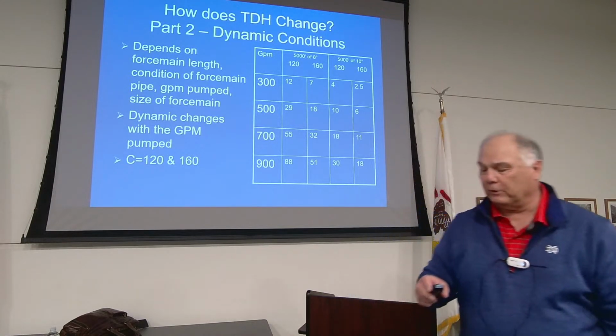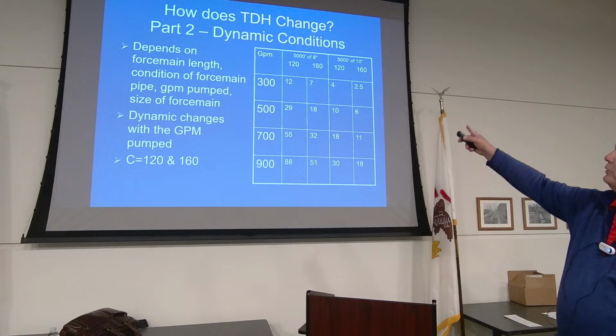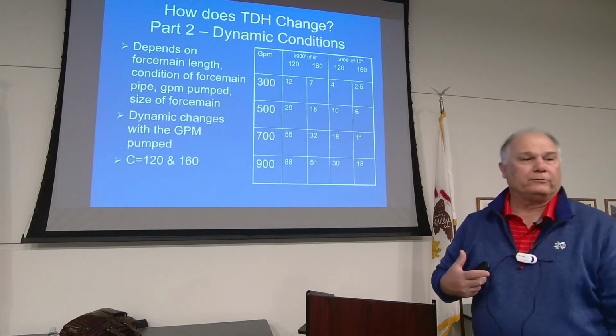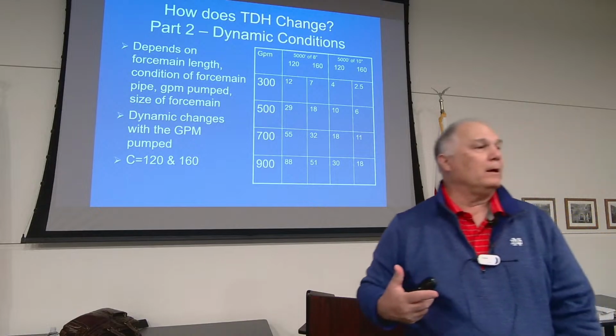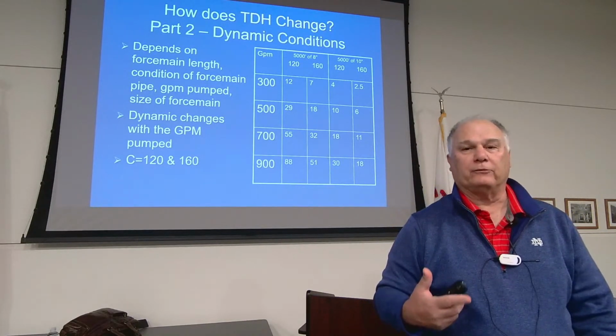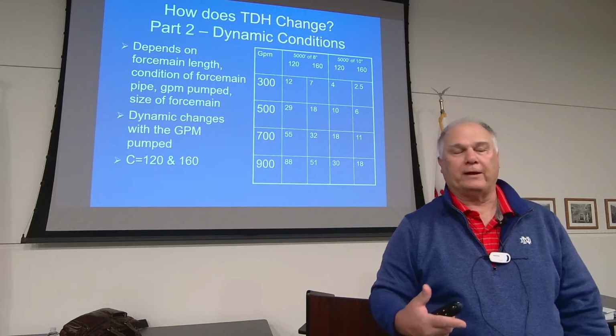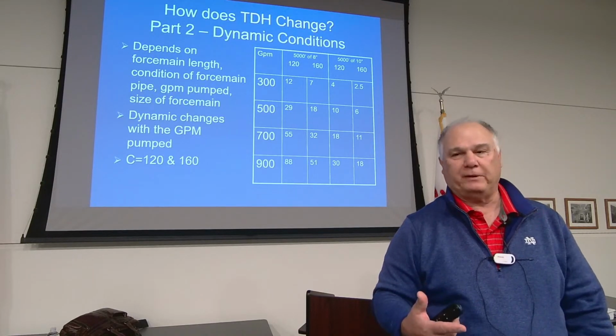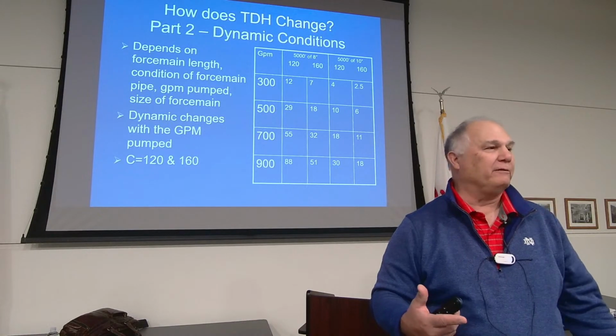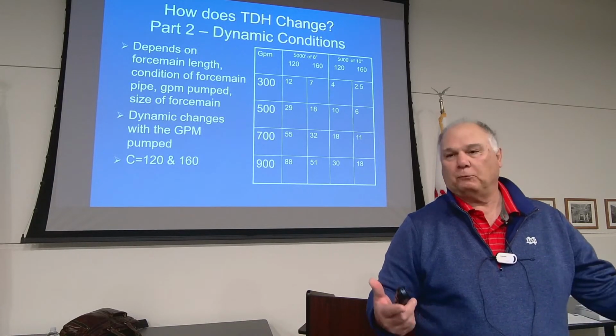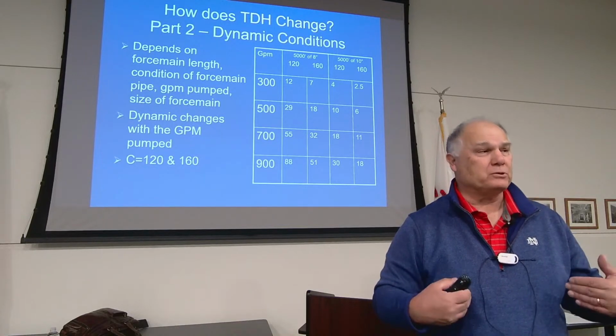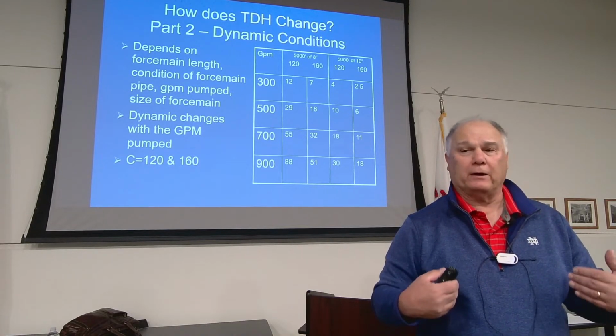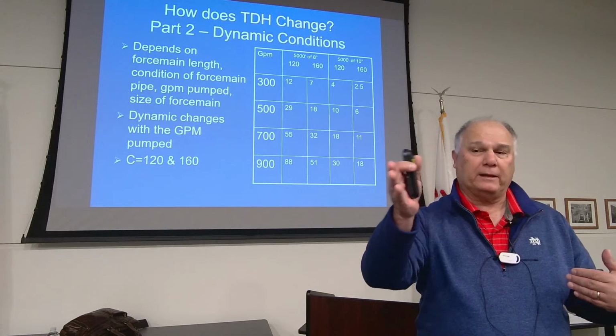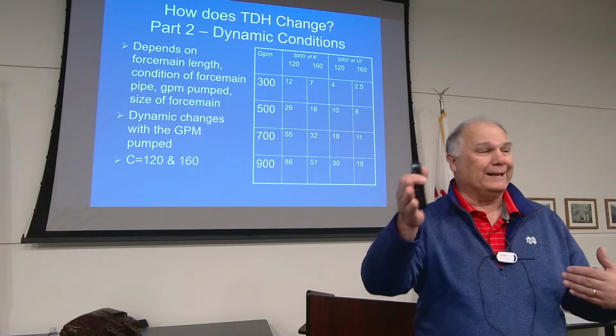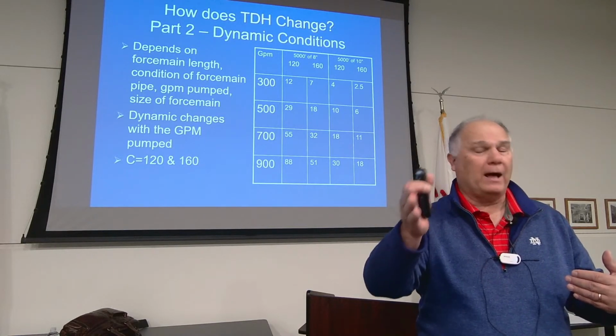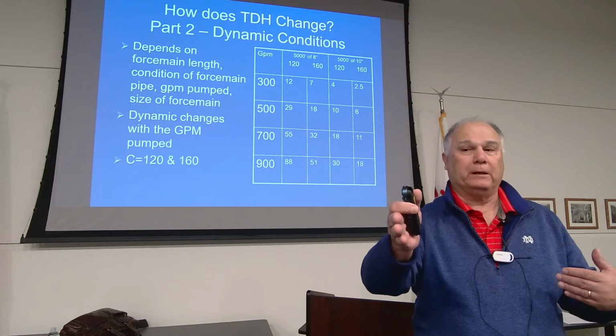So when we look at stations, we look at two different C factors. In our business, in the pump world, Illinois EPA says we've got to design our stations for a C factor of 120, which is a piece of PVC pipe or a piece of pipe that's been in the ground for 20 to 50 years. Okay, we can do that. But as pump suppliers and designers, we've got to understand that we just can't design right at the edge for horsepower, because we're going to exceed that pump station volume at the very beginning.